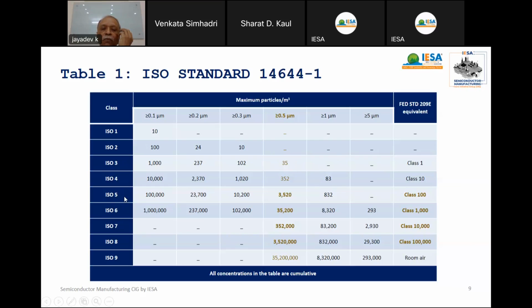Normally we are more familiar with ISO 5. It is nothing but class 100. You see here Federal Standard 209E. Normally we talk in these terms because class 100, class 1000, 10,000 are easy to spell and understand.